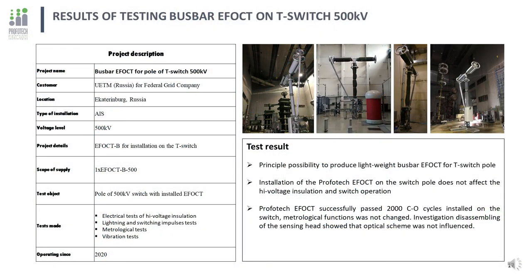Vibration is one of the critical factors influencing electronic and optical equipment. Due to its light weight and other advantages, it is advisable to locate EFOCT directly on the high-voltage switch pole to eliminate dead zones of protection. Profotech developed a busbar EFOCT for the Federal Grid Company of Russia that can be easily installed on a 500 kV T-switch pole. The test EFOCT mounted on the switch successfully passed all necessary high-voltage type tests in dry and wet state, and then passed a long endurance test of 2000 CO switching cycles. The EFOCT was in full operation during the entire test with test current injected and metrological functions checked. After disassembly of the sensing head, no damage was found, and Profotech EFOCT is now considered ready for pilots as a directly-on-switch mounted solution.